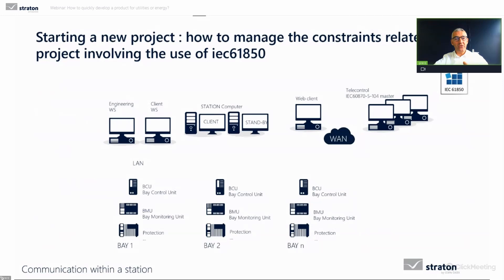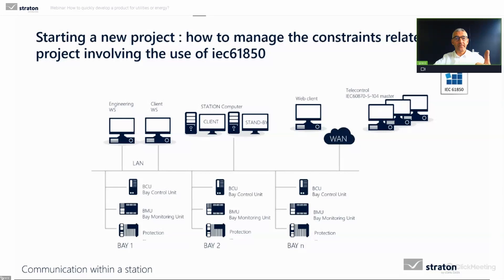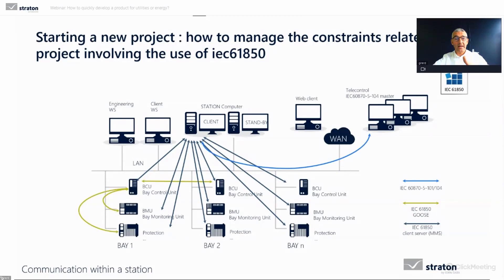Let's look at a typical topology of equipment in an electrical substation. You have controllers and stations — different kinds: BCU and protection, bay controlling units or bay monitoring units. These are connected through an Ethernet network. Controllers communicate with each other using the GOOSE protocol. Communication on IEC 61850 client-server is through MMS.